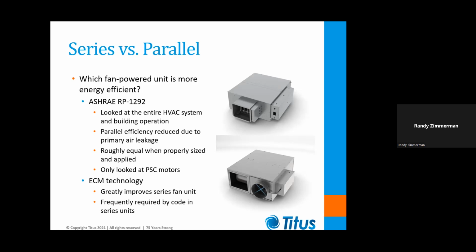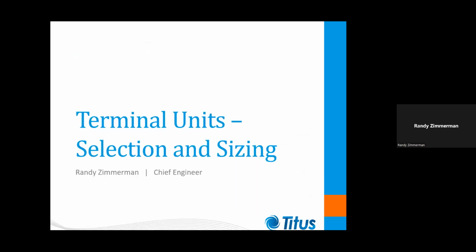Unfortunately, that is pushing some customers to switch from series to parallel so that they can use the less costly but much less efficient PSC motor. So to me, it's a bit of false economy because you're trying to dodge modern technology, which is more efficient, for a short-term reduction in first cost, whereas you're probably going to be paying for that first cost through lower efficiency for the life of the building. So I'm not a big fan of that.